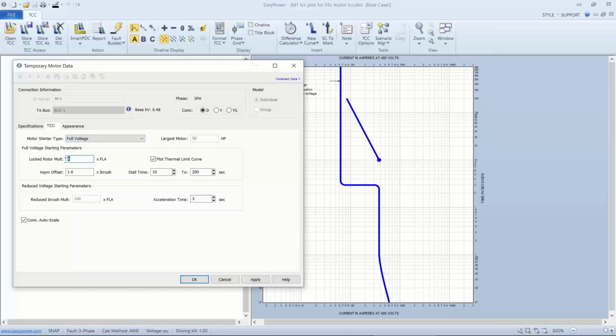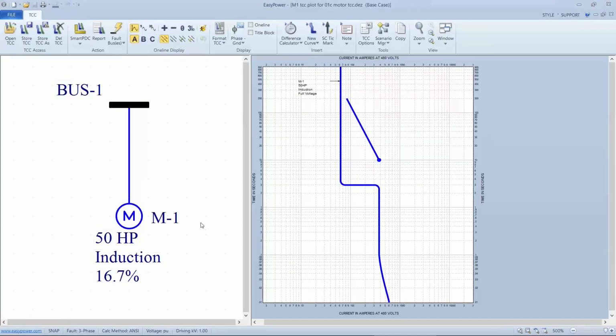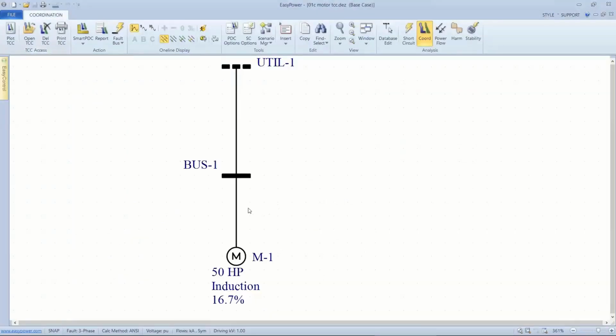And then if we have different locked rotor multipliers, now these are used for voltage drop calculations in load flow and for starting curve protection plots for coordination. Okay, so that's the motor starting curve. So far we've covered the TCC definitions for transformers and motors. We've looked at the keystone points for transformer damage curves for single and three-phase low faults. And I think that's everything I wanted to cover in this particular session.